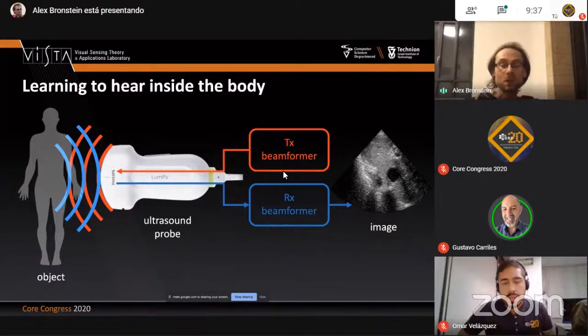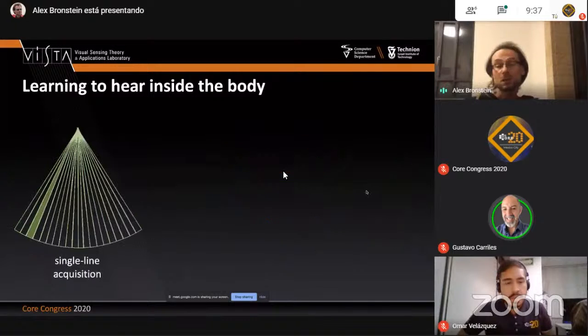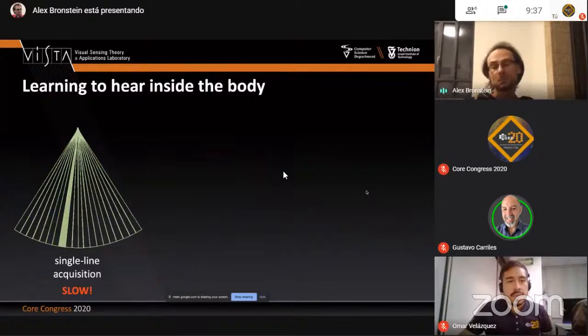And the regular way to acquire an ultrasonic image is by focusing a beam and then sweeping with this beam. This is called B-mode scan, typically. The problem with this single line acquisition technique is that it is slow. And if you need to image fast-moving targets, like, for example, cardiac imaging, this can be prohibitively slow. So we need to do better.